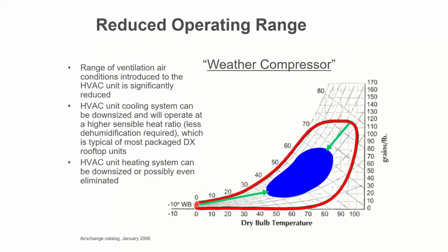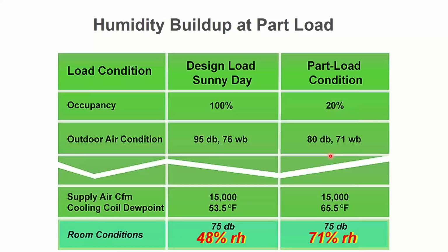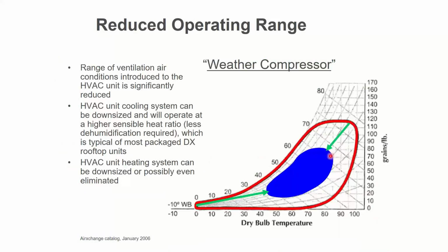However, when I have an ERV, it preheats it and/or pre-cools it and/or dehumidifies it and/or humidifies it. And now my HVAC equipment selection is a smaller piece of equipment, and it only has to do the work of the blue bubble now, because the ERV is trimming all the sides down to make this guy a little bit more appropriately sized for more moments of the day. So instead of having this part load condition be a problem, it actually works out pretty well if you have an ERV, because your part load condition doesn't seem much different than your regular condition from the compression standpoint.